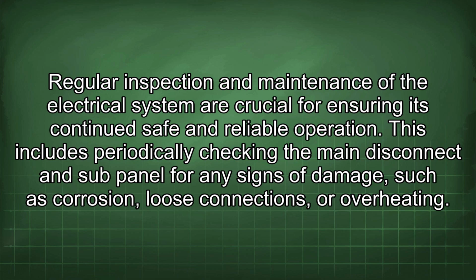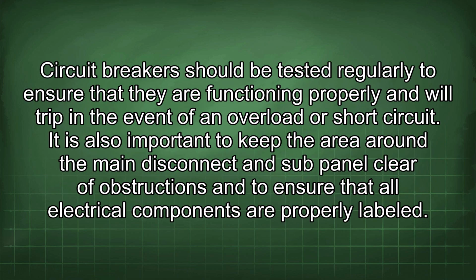This includes periodically checking the main disconnect and sub-panel for any signs of damage, such as corrosion, loose connections, or overheating. Circuit breakers should be tested regularly to ensure that they are functioning properly and will trip in the event of an overload or short circuit. It is also important to keep the area around the main disconnect and sub-panel clear of obstructions and to ensure that all electrical components are properly labeled.